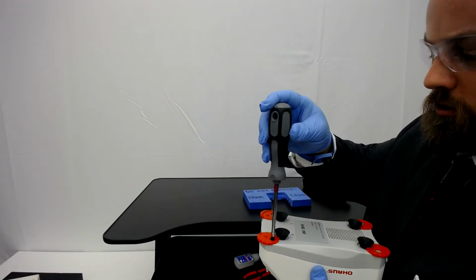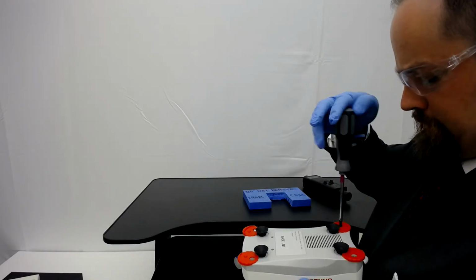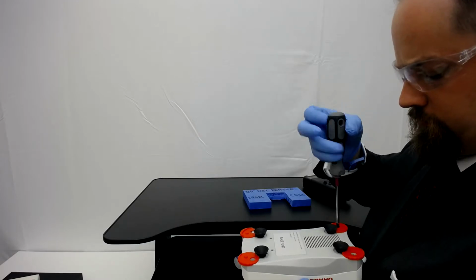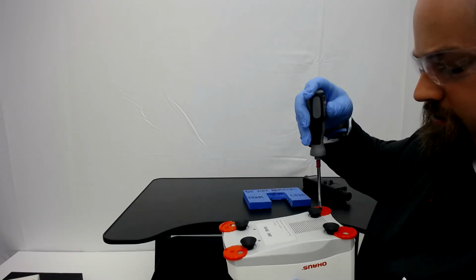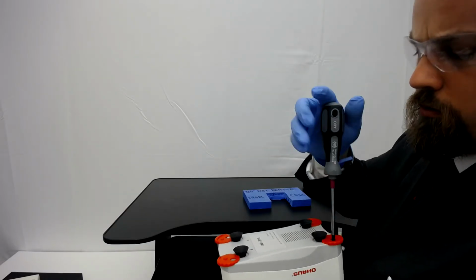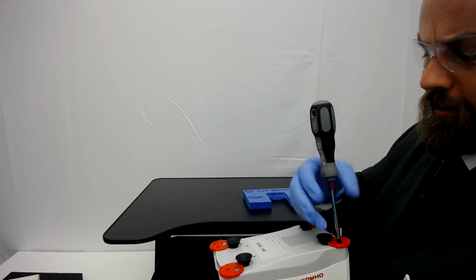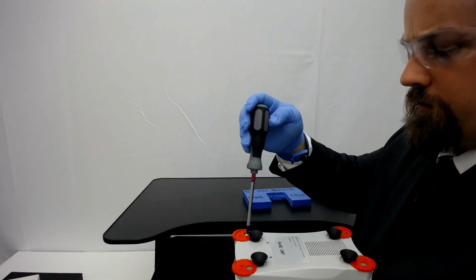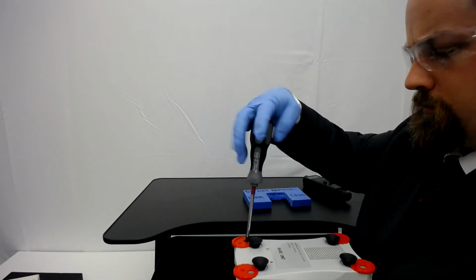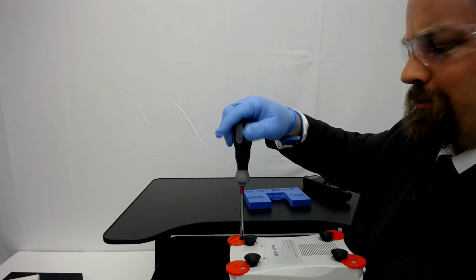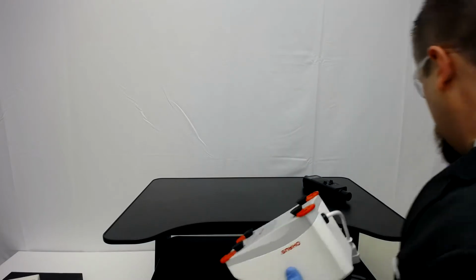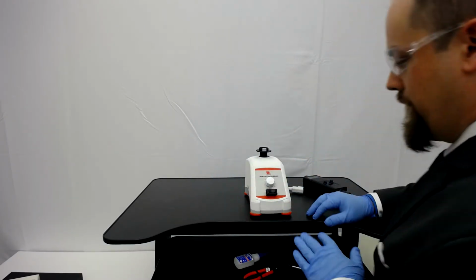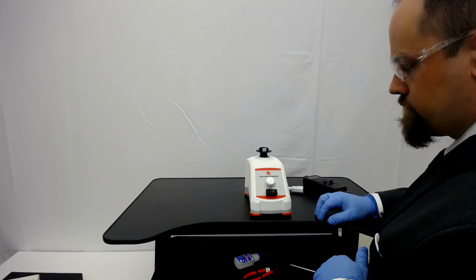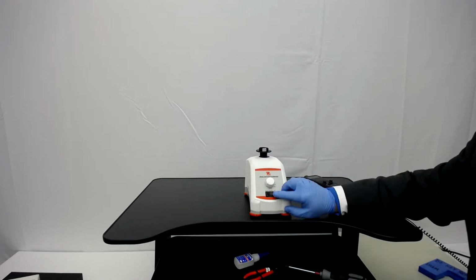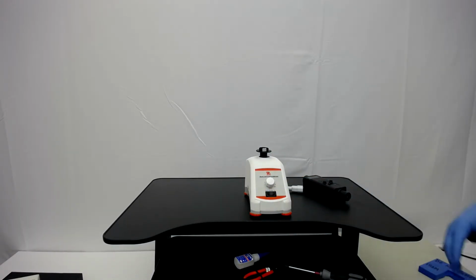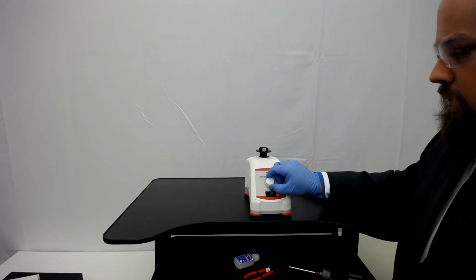And you will want to also use the proper torque specified in your manual. The Loctite 248 just stops the screws from vibrating back out. We use Loctite on most of our units, particularly any unit like this that vibrates significantly. Once the unit is reassembled, you then want to go back and do all your testing again to make sure that it passes. Once you have put in the screws, just pop the switch back in and you're ready to go. And it's the same round of tests for your final check.